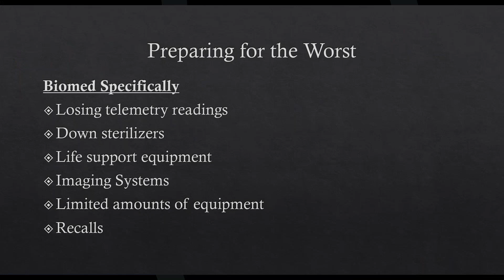You will run into a patient incident, and so error logs, for example, pulled off of the Alaris software will indicate what happened. Certain times nurses will accuse equipment of malfunctioning, when in reality it was a lack of communication. Imaging systems are the fastest solution for internal diagnostics and the most intense devices to repair due to limited systems and complex repairs, with an even faster need for turnover time. Limited quantity equipment must have parts on site at all times to reduce turnover time.